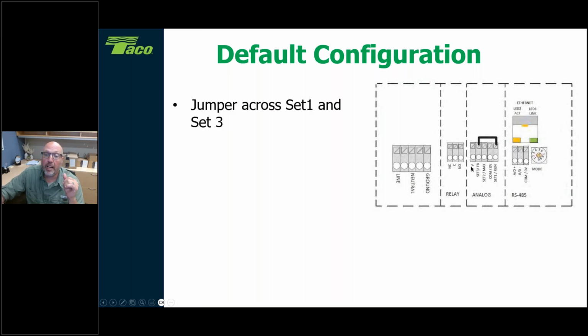So your default configuration, like I talked about, you've got your jumper across set 1 and set 3 here, okay? You're going to bring line voltage in. The default mode dial is going to have is 1. Just leave that alone. And whenever we change any of the settings on this mode dial, and there's a couple of times that we're going to, you have to make sure you power down the circulator, meaning remove power. All right, this mode dial is only read on startup. It is not read continuously, and there's a lot of products out there that only read configurations on a startup. It's not continuous. So this circulator we've been doing now for almost 14 years, and we have this mode dial. Just remember, all right, when you want to change settings and use one of the other modes, the only other modes you're really using is 1, 2, and I think I did something with 0. All right, and that's it. But when you change that mode, power down, power it back up again.